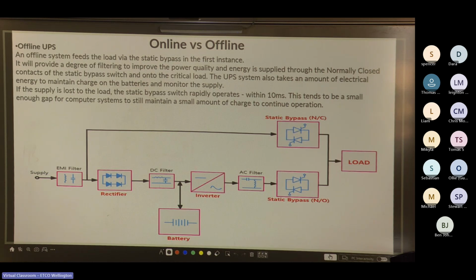So you've got some different components here. You've got an EMI filter on the supply. It feeds a static bypass, which is normally closed, and then goes to the load. And then you've got your rectifier, your DC filter, battery, inverter, another AC filter, and the static bypass, normally open contacts. So when the static bypass triggers, because there's loss of supply, the normally closed contact opens, the normally open closes, and the battery begins to feed the load.